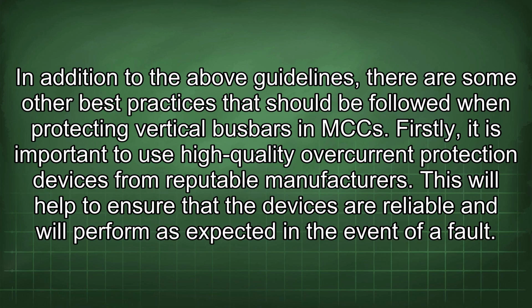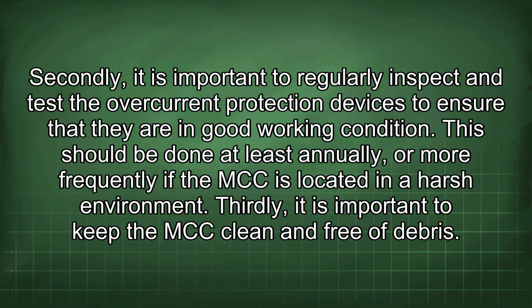In addition to the above guidelines, there are some other best practices that should be followed when protecting vertical busbars in MCC. Firstly, it is important to use high-quality overcurrent protection devices from reputable manufacturers. This will help to ensure that the devices are reliable and will perform as expected in the event of a fault. Secondly, it is important to regularly inspect and test the overcurrent protection devices to ensure that they are in good working condition. This should be done at least annually or more frequently if the MCC is located in a harsh environment. Thirdly, it is important to keep the MCC clean and free of debris.